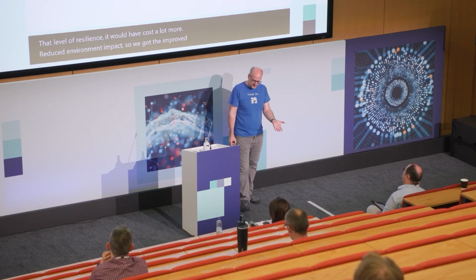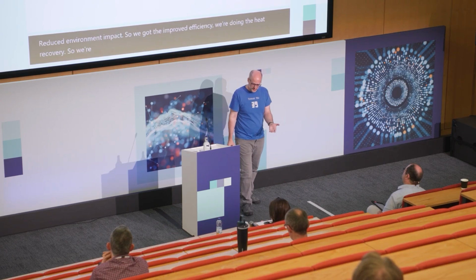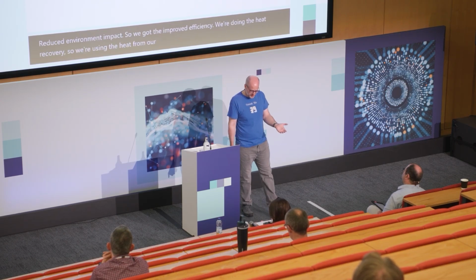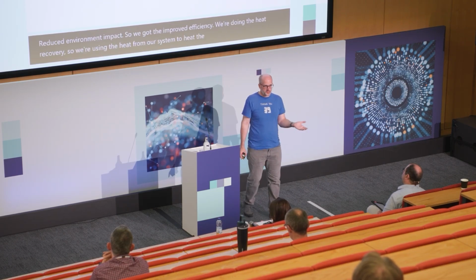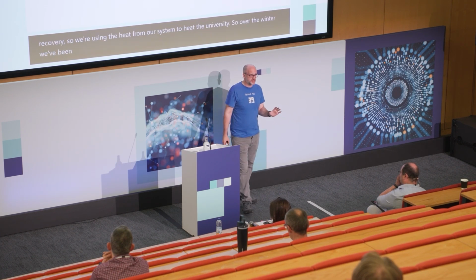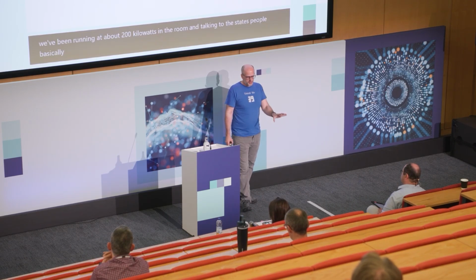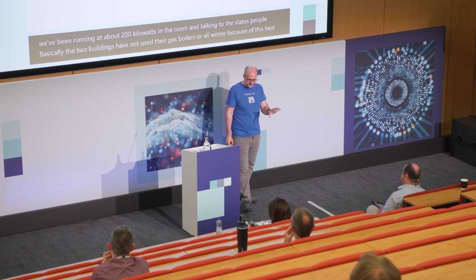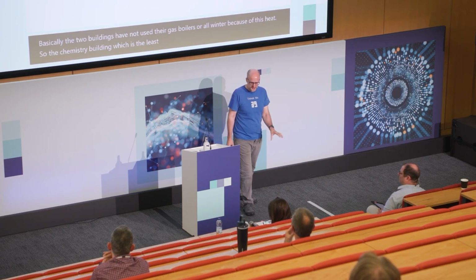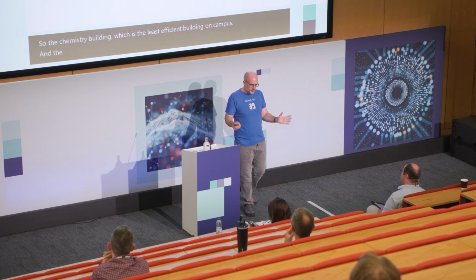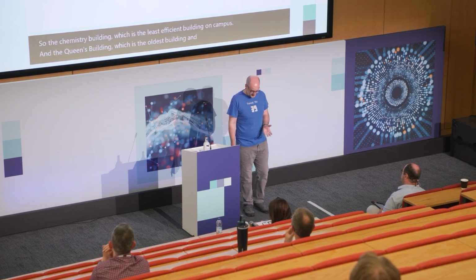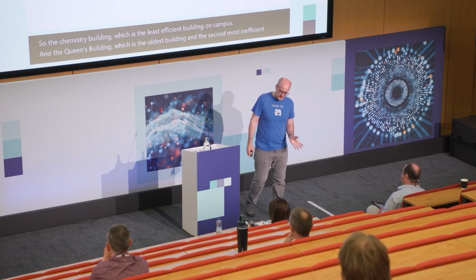We're doing the heat recovery. So we're using the heat from our system to heat the university. Over the winter, we've been running at about 200 kilowatts in the room. And talking to the estates people, basically the 2 buildings have not used their gas boilers all winter because of this heat. So the chemistry building, which is the least efficient building on campus, and the Queen's building, which is the oldest building and the second most inefficient building on campus, haven't had to use their boilers.